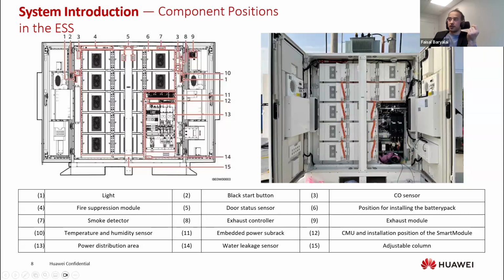The sensors and most of the wirings are already on the cabinet from the factory, and even the power distribution unit is there. But of course we have to make the connections between the PCS and the DC rack controller on the bus side, inside the power distribution unit. The modules, the copper bars, and the communication between them are the ones we have to assemble ourselves.